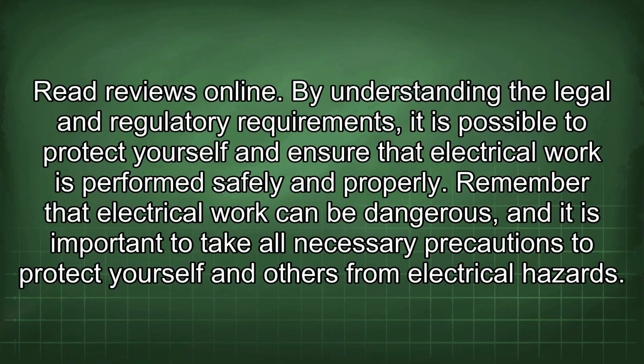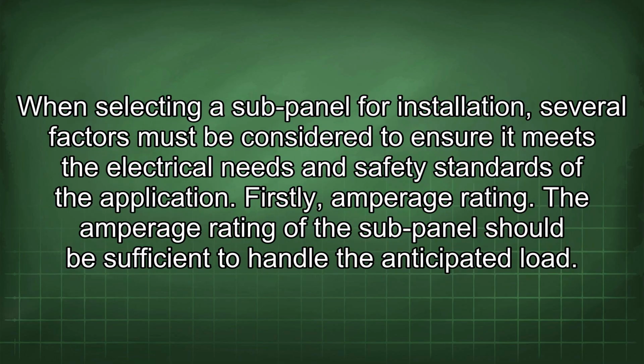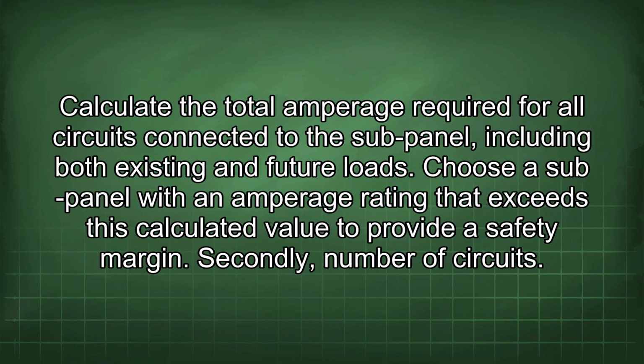others from electrical hazards. When selecting a sub-panel for installation, several factors must be considered to ensure it meets the electrical needs and safety standards of the application. Firstly, amperage rating. The amperage rating of the sub-panel should be sufficient to handle the anticipated load. Calculate the total amperage required for all circuits connected to the sub-panel, including both existing and future loads. Choose a sub-panel with an amperage rating that exceeds this calculated value to provide a safety margin.